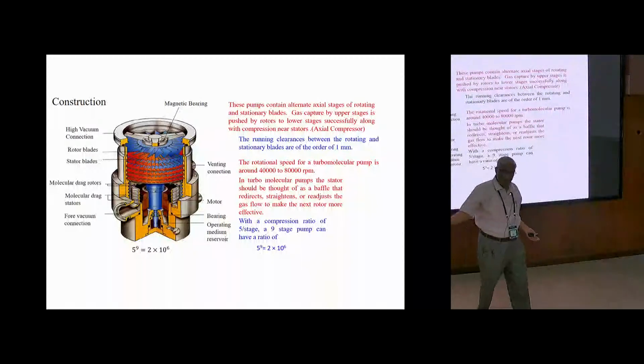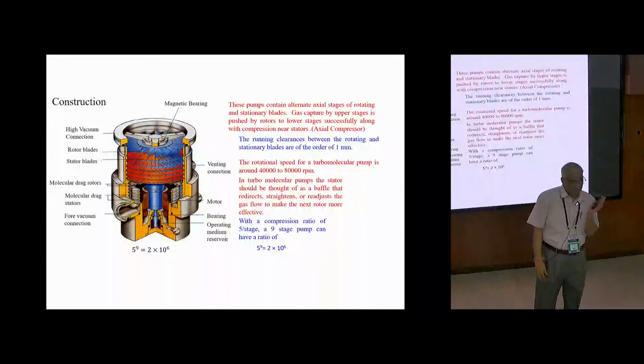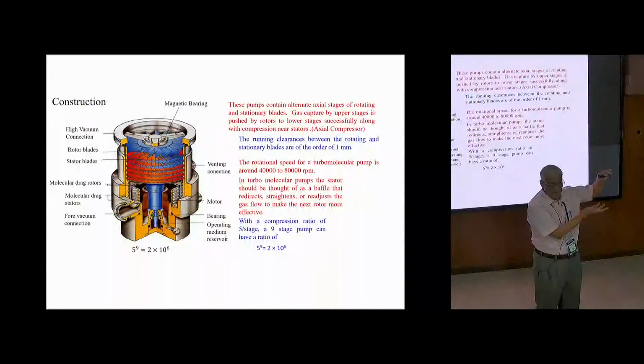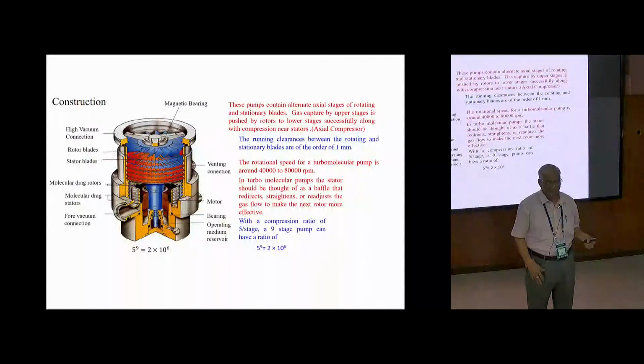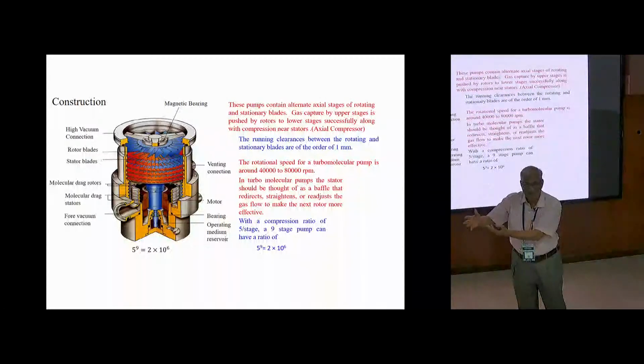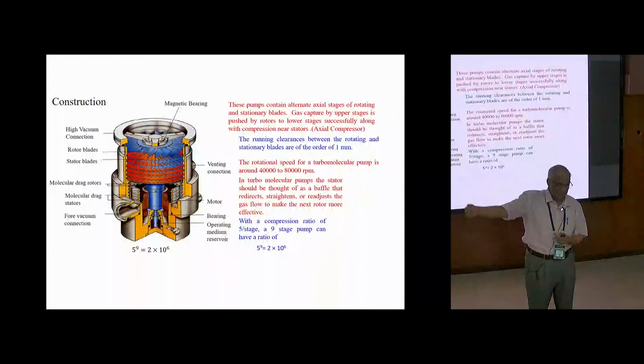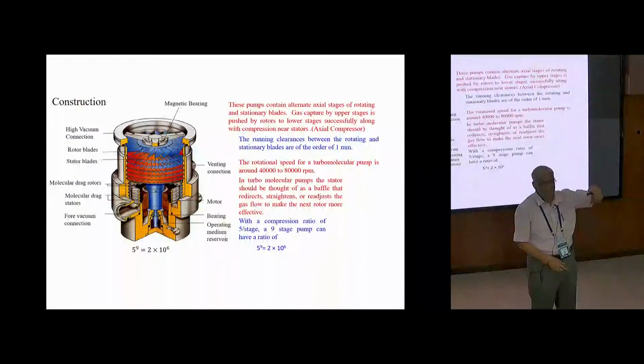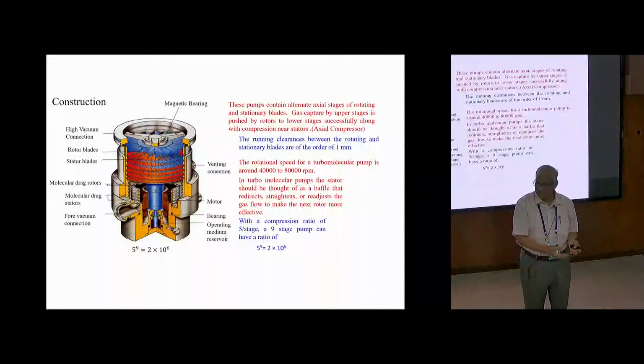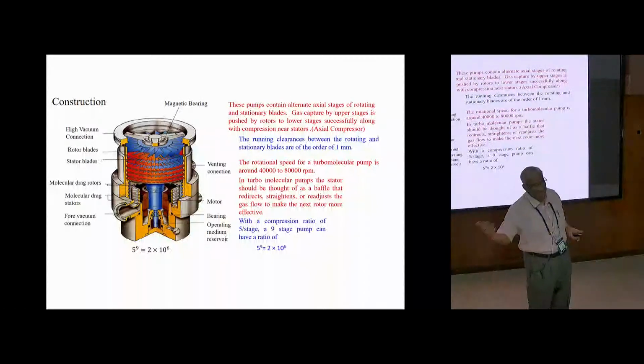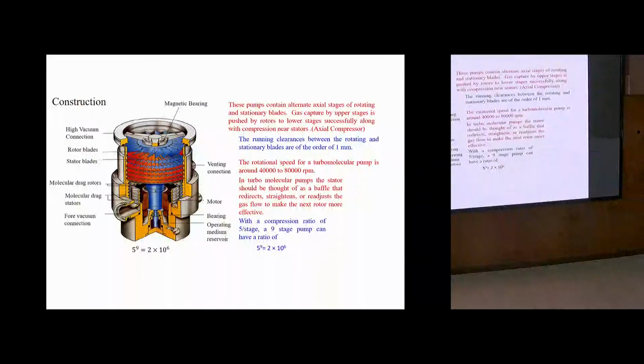Lot of molecules are going from pump to chamber. From chamber to pump also they are coming. But chamber is 10 power minus 7 torr, pump is 10 power minus 8 torr. On a net equilibrium, statistical modeling, if you do minus 7 torr, the X molecules come in the X direction, in the 360 degrees, towards the pump. 0.9 X only come this side, because molecules are fewer. So there is a net probability in the pump. So this is how the turbomolecular pump mechanism itself is different.